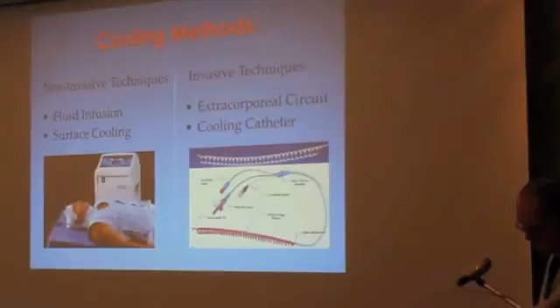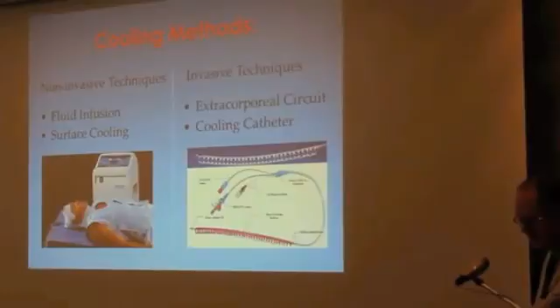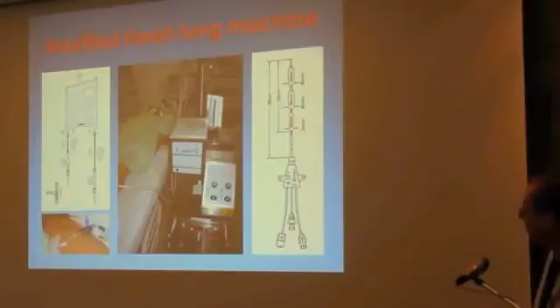You can do this with non-invasive or invasive techniques, rapid cold like before, or you can use intravascular cooling catheters with an extracorporeal circuit, and this is what we did. We use a flat sheet heat exchanger, it's here, combined with an old heart-lung machine that we didn't need for the cardiac surgery unit, and a very thin and long catheter. We stuck a rivet on the front panel in a manner that the knob cannot exceed 25 RPM to make sure that the 2.6 millimeter thin catheter may not be damaged by a high water flow, and thus water may not go into the circulating blood.